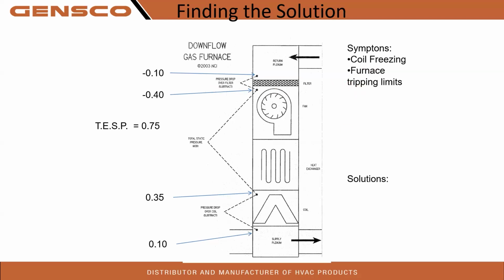So why are we tripping the limit switch? Looks like our 0.1, so we got a 0.3 over that filter. Filter too small. Boy, we see that a lot too. I'm going to show you a chart on 20 by 20 by 1s, our max CFM. If I go out to a job site or I see a 20 by 20 by 1 on a 4-ton system, I'm going to go right towards that filter sizing. Filter media is too restrictive. That's going to drop back to our MERV 13 air question. Higher the MERV, the more restrictive.